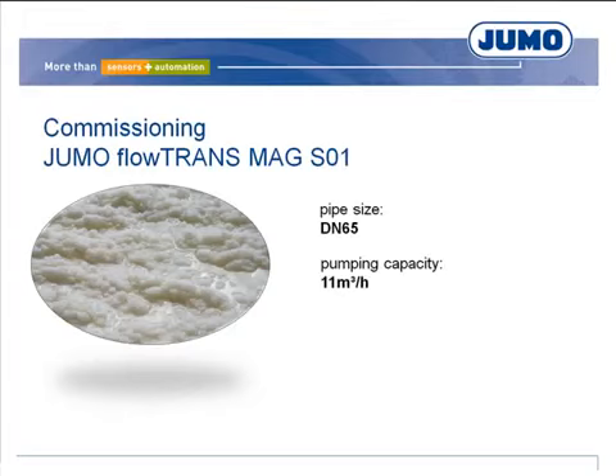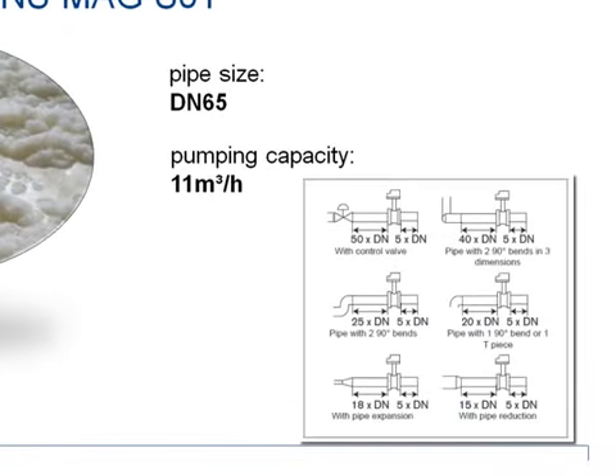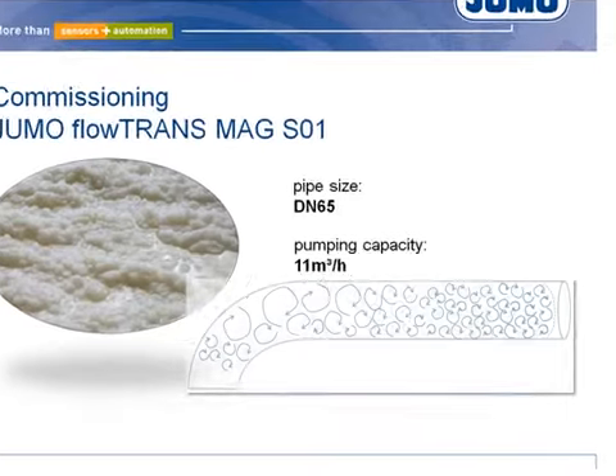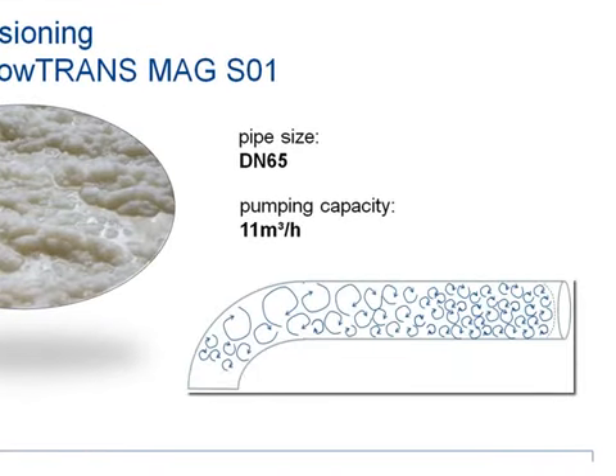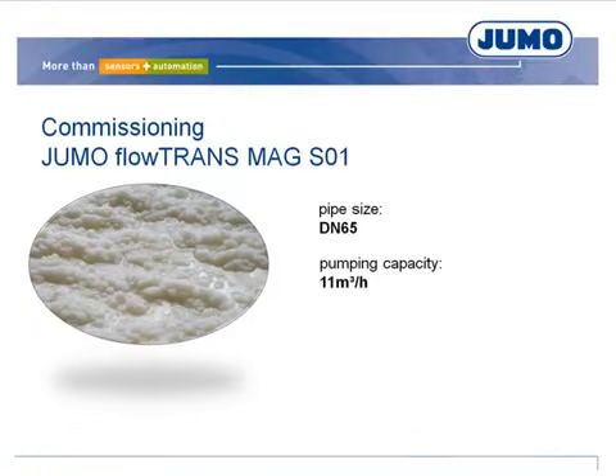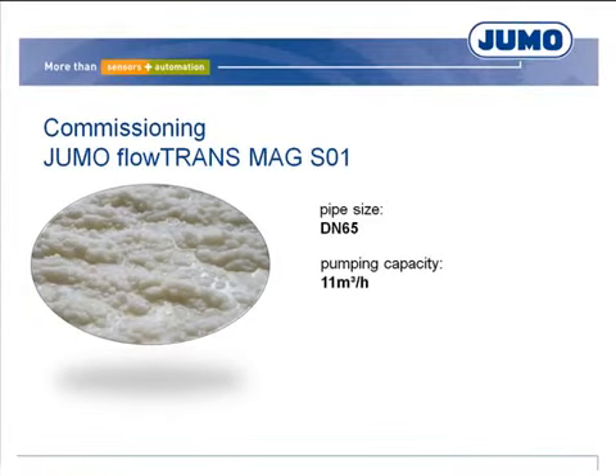Each flow meter requires a most possible uniform flow profile. Therefore, so-called inlet and outlet sections are needed to calm the flow after being swirled by bends, taperings, valves, or having undergone angular momentum.